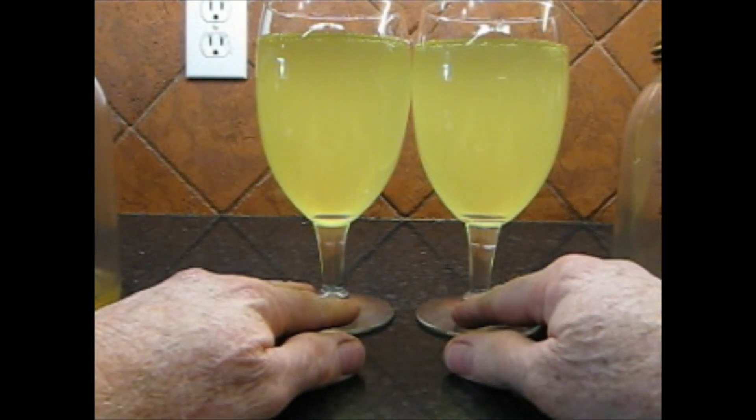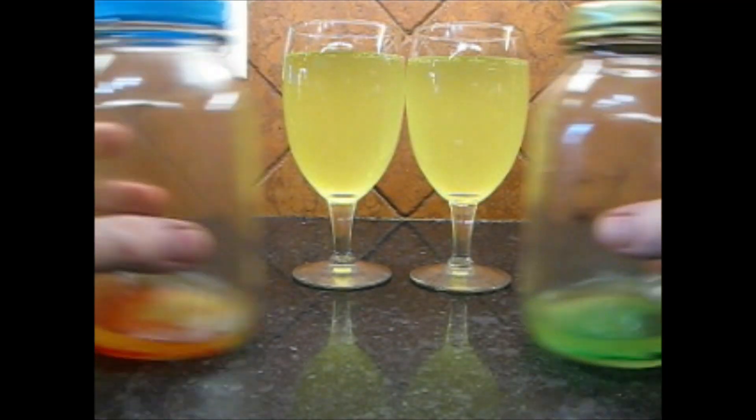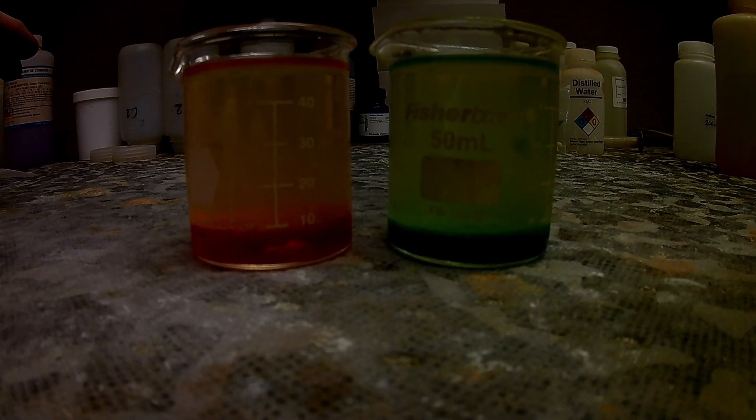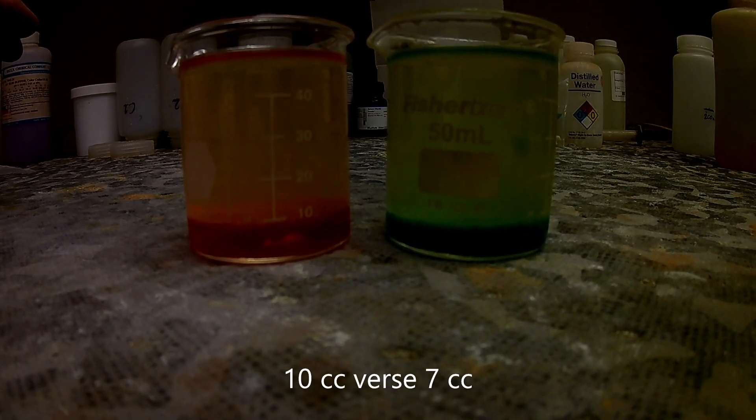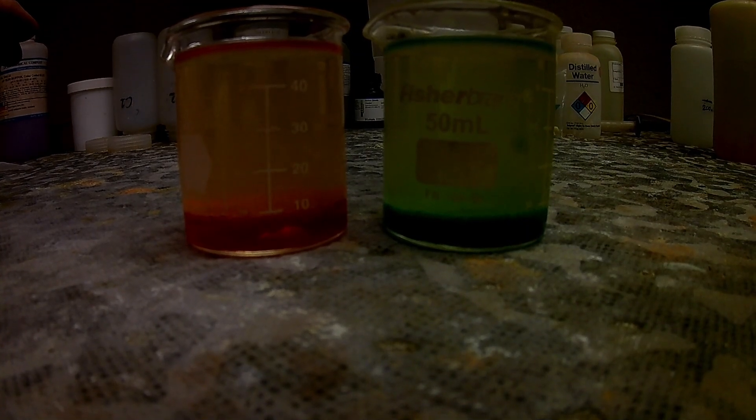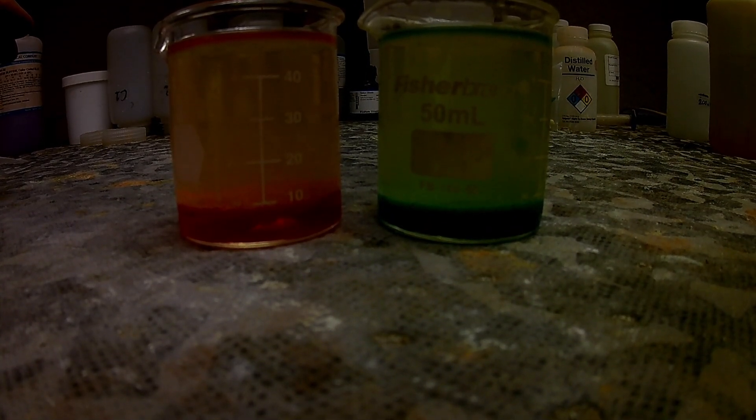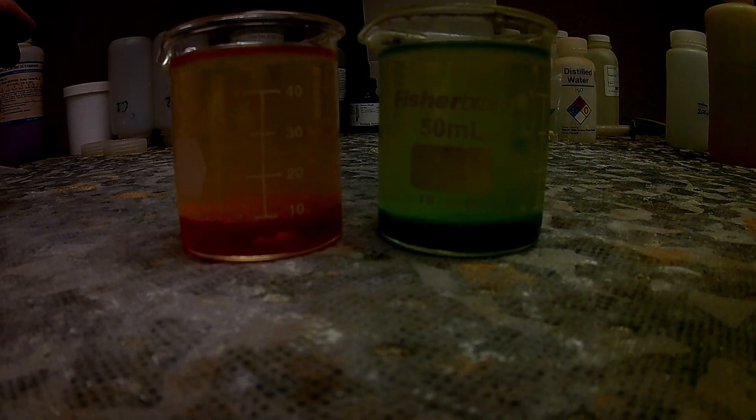Here's what remains. This is the result of the restriction on the return line to the vacuum pump. The red is without restriction, the green is with restriction. You can see that the green is a little bit less, but not by very much. So the question is, is it worth running the restriction and getting just a little bit less water back in the vacuum pump and adding an additional six hours of run time on your machine? I think the cost of run time supersedes the savings of having a restrictor on that. So it works, but it's not economically feasible to do this.